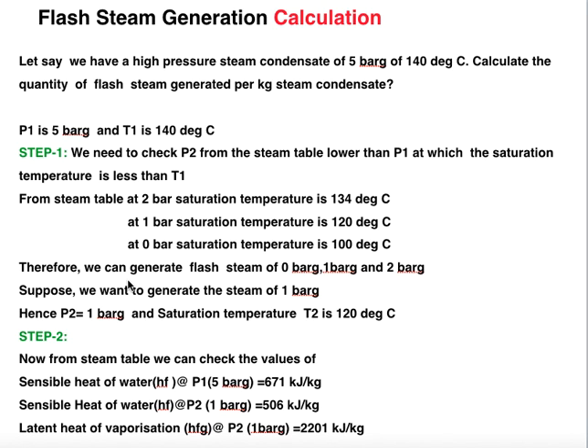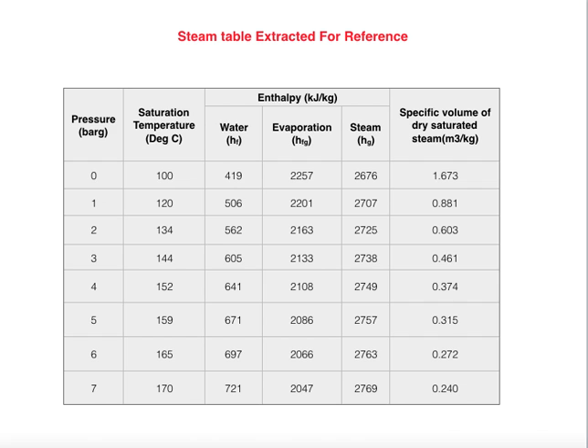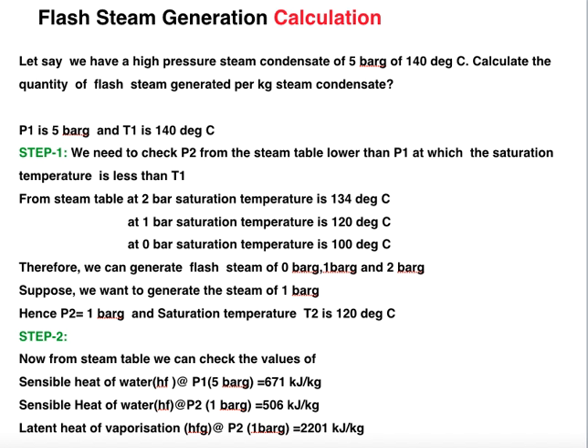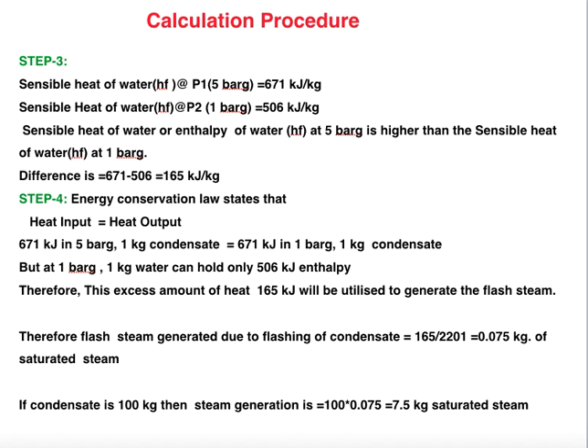In step 2, from the steam table we read the sensible heat of water at P1 and P2, and the latent heat of vaporization at P2. At 5 bar gauge (P1), the sensible heat HF(P1) is 671 kJ/kg. At 1 bar gauge (P2), the sensible heat HF(P2) is 506 kJ/kg, and the latent heat of vaporization HFG(P2) is 2201 kJ/kg.